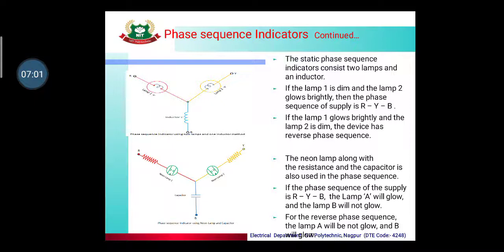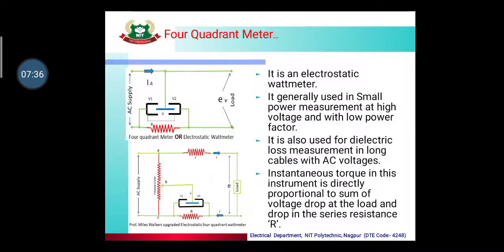In the second static type figure, neon lamps are used along with resistance and capacitor. Here, if the phase sequence is correct — that is R-Y-B — lamp A glows and lamp B does not glow. If the phase sequence is disturbed or reversed, lamp A does not glow and lamp B glows. These indications tell us the phase sequence of the supply.